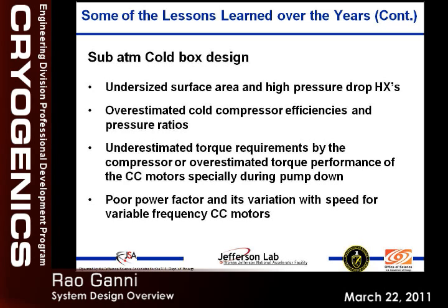And separating that out and navigating ourselves through this very torturous map, it's a forest. You can't see any light, because it can be the power factor or it can be the surge curve which is tripping you on any one of the 5 in series. So it's extremely difficult to put your finger on and say, this is where I need to correct it, even to separate it out. That's one of the things we spent a lot of time sorting out. Although if it is a single compressor, yes, I can see we could have separated it much more easily. Because there are 5 in series and the surge curves are on top of each other, it was extremely difficult for us to separate it out.